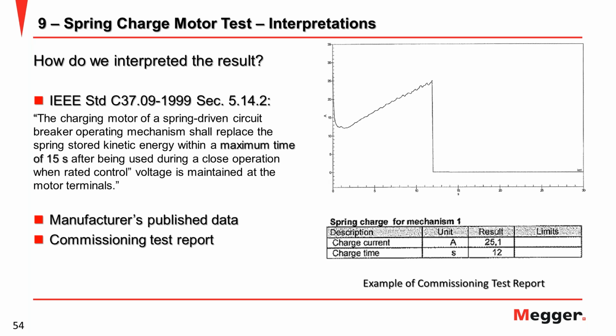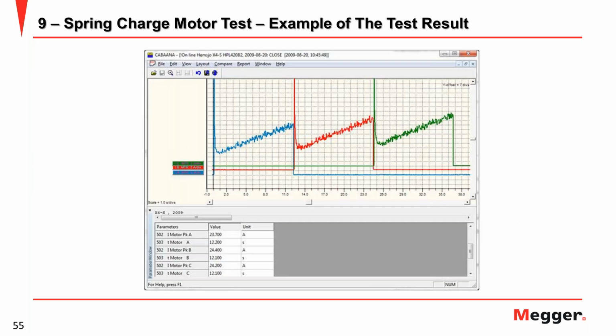Yeah, this is also important because you can define the problem on the motor. Otherwise, the breaker cannot operate because the motor cannot charge after a close operation. This is an example from our equipment. You can see the current changing when the motor starts to operate. Current is very high, and then goes down and increases again until the breaker motor stops.